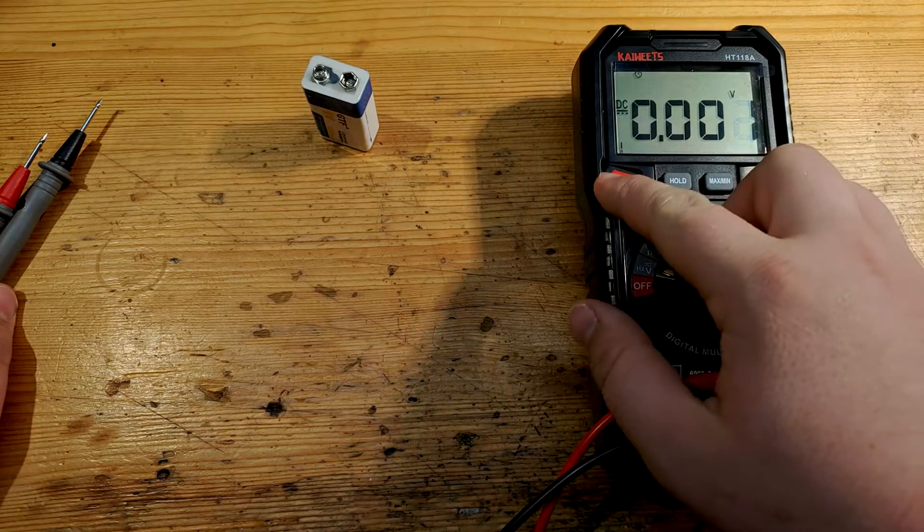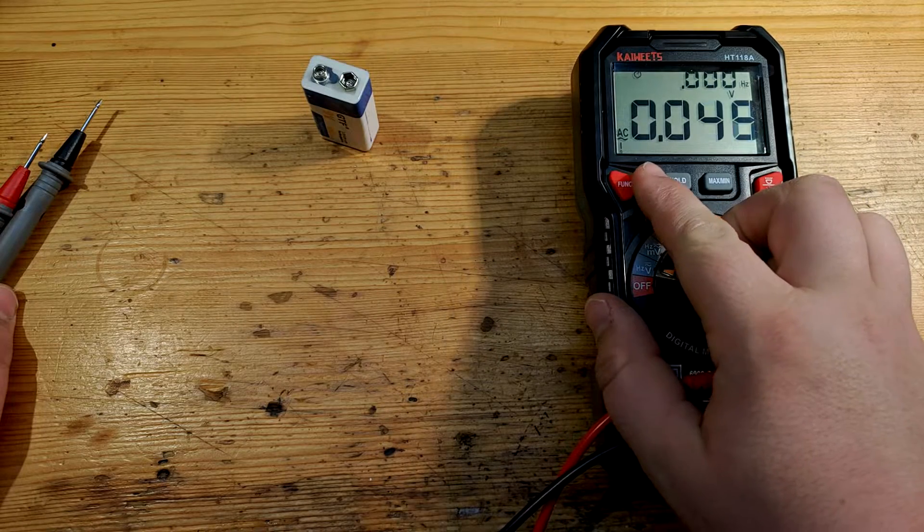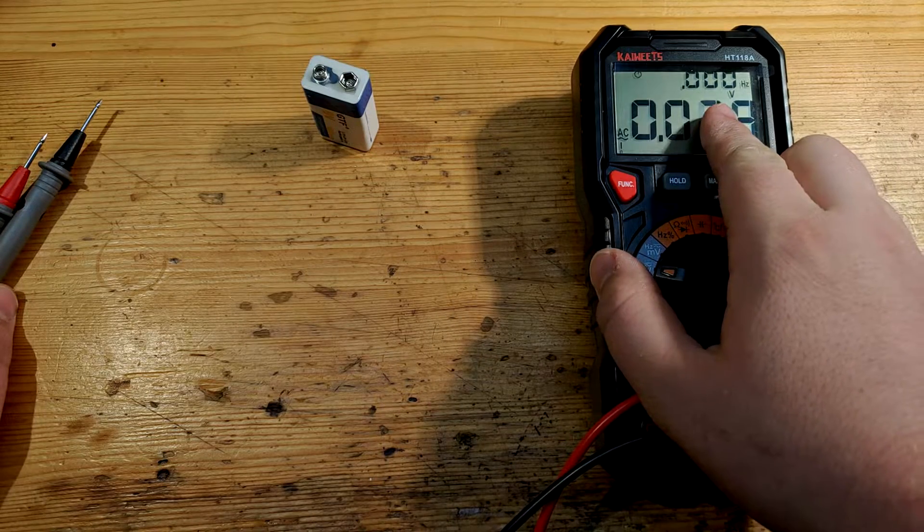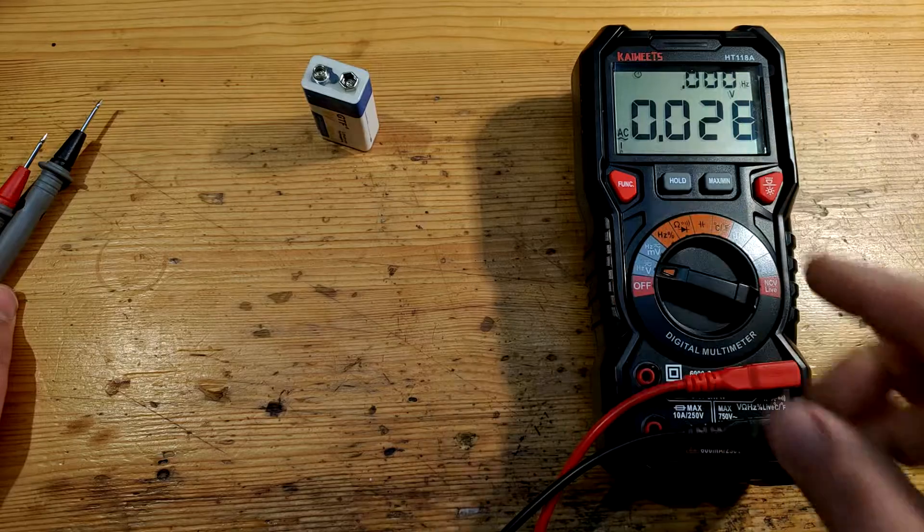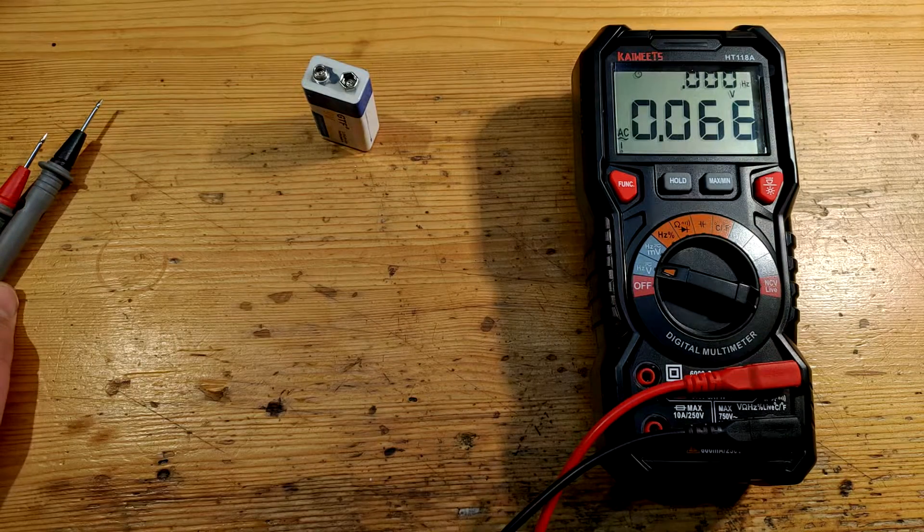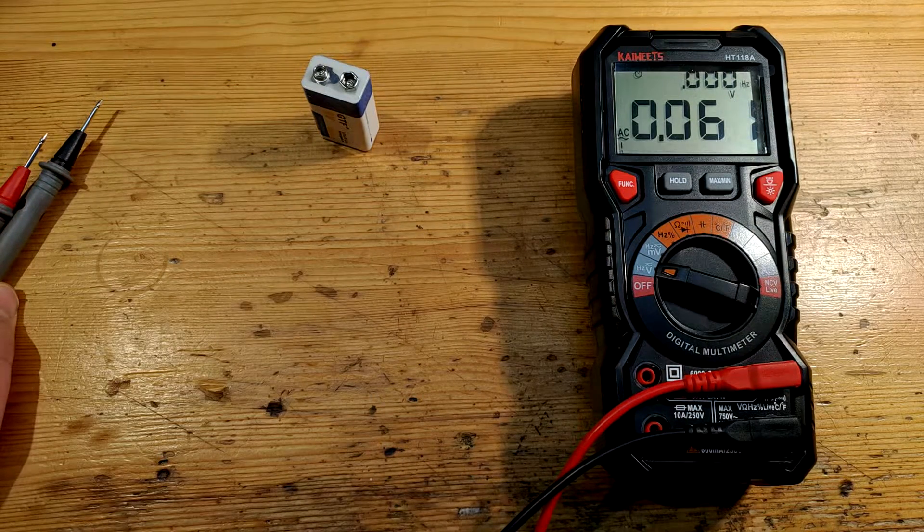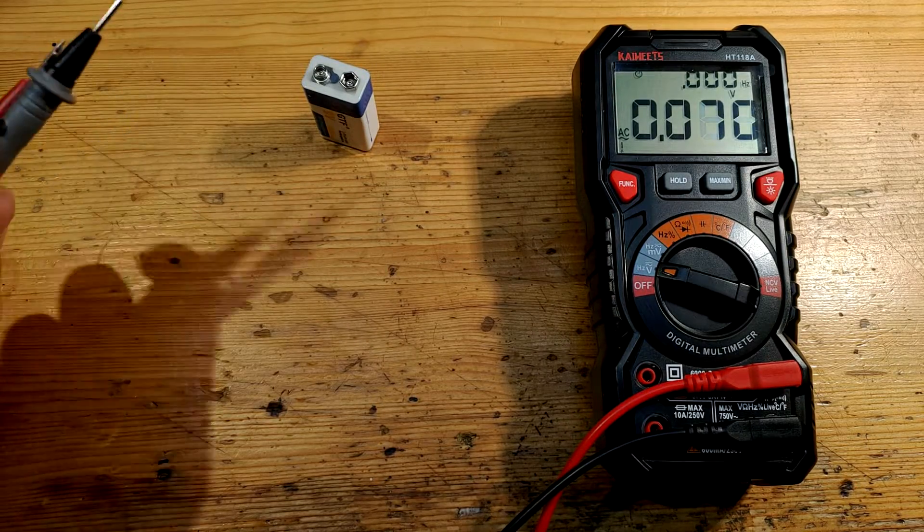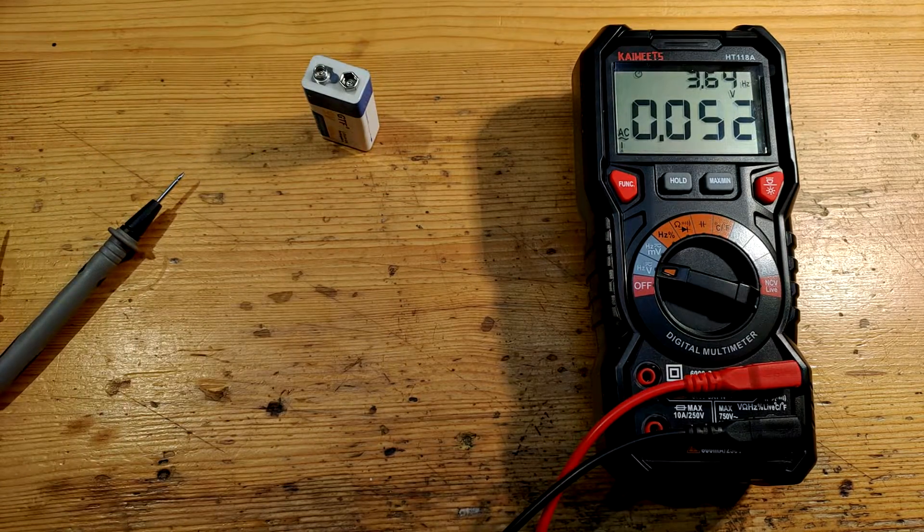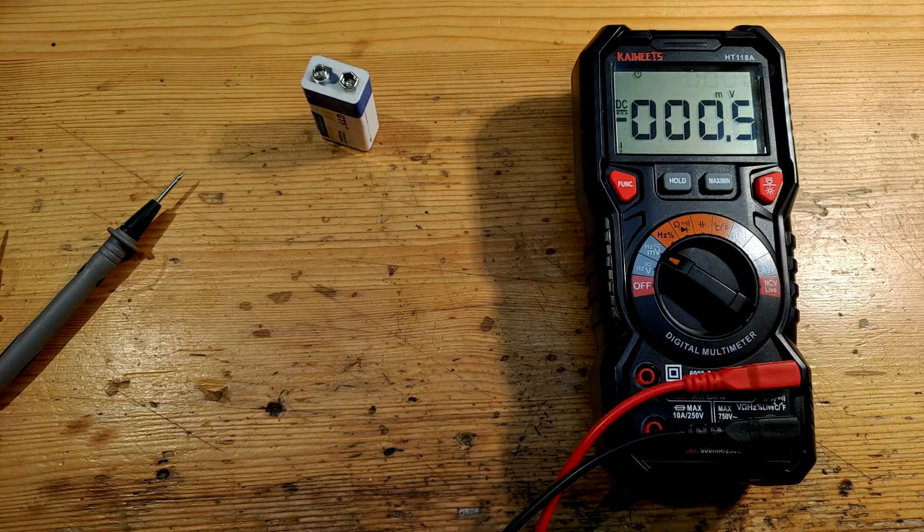After switching to AC, the secondary display begins showing measured frequency. And if the measured voltage is above 80V, the display is backlit with orange light. Input resistance is 11 megaohms for volts and 7 megaohms for millivolts.